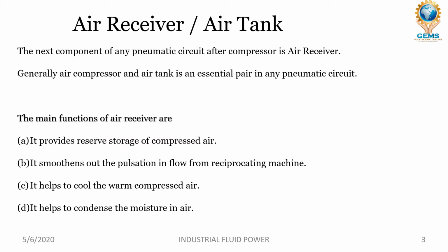Air receiver or air tank. The next component of any pneumatic circuit after compressor is air receiver. Generally, compressor and air tank is an essential pair in any pneumatic circuit. The main functions of air receiver are: it provides reserve storage of compressed air, it smoothens out the pulsation in fluid flow from reciprocating machine, it helps to cool the warm compressed air, it helps to condense the moisture in air.